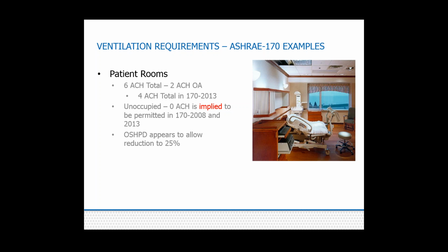One other item in Standard 170 is that in 2013, for patient rooms, it reduces the total air changes to 4, which can be a significant energy savings. So maybe if you can talk your local code authority into letting you step up to the newest code, you might be able to save some energy.